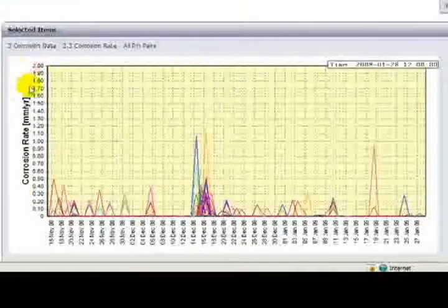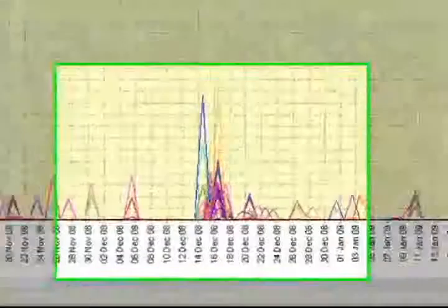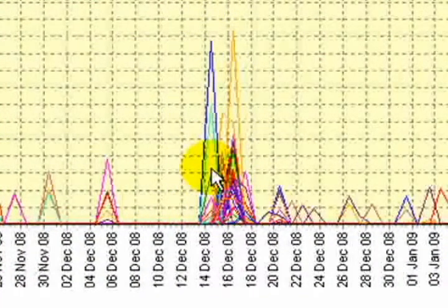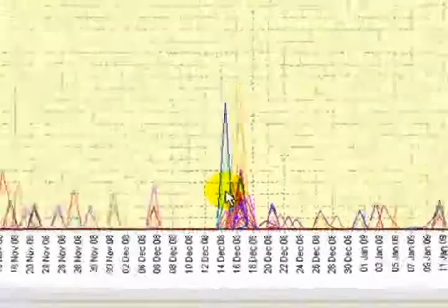Looking at the next graph, we can examine the rate of change of the accumulated wall loss, or in other words, the internal corrosion rate. The bursts of activity seen in this graph, while relatively small, could be linked back in time to corrosion mitigation efforts like cleaning pig runs or chemical inhibitor performance.